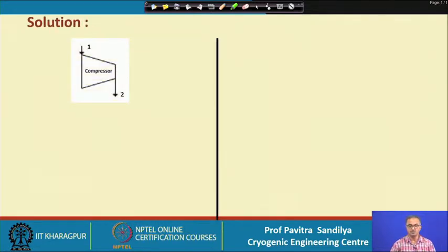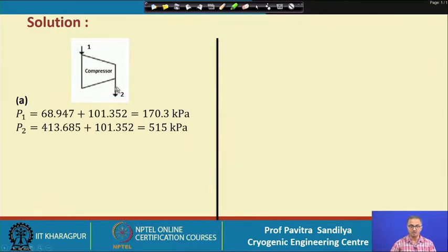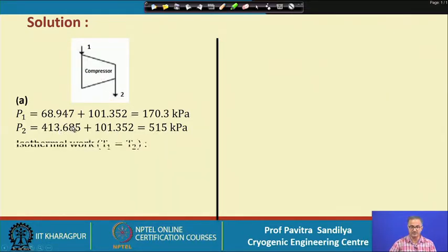This is a typical compressor where points 1 and 2 represent the inlet and outlet. P1 is the inlet gauge pressure — we add atmospheric pressure to get the absolute pressure. Similarly, P2 is the outlet gauge pressure plus atmospheric pressure to get the absolute value. With P1 and P2 known, and since it is isothermal compression, T1 equals T2.